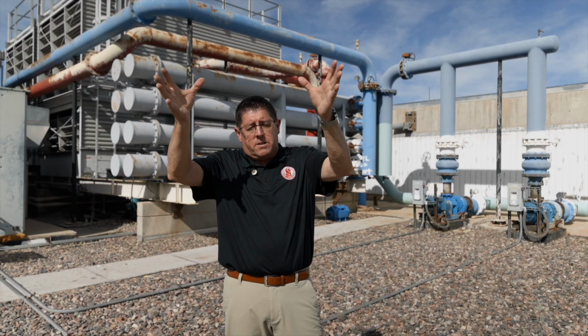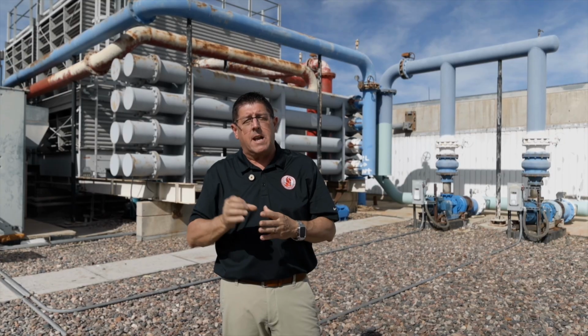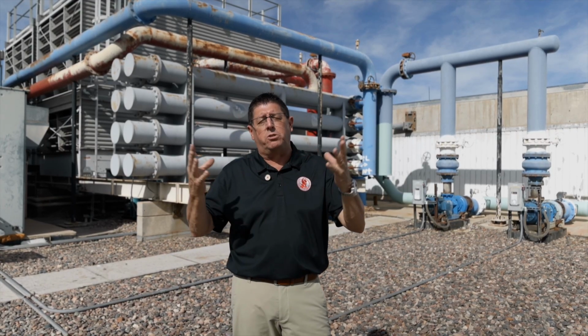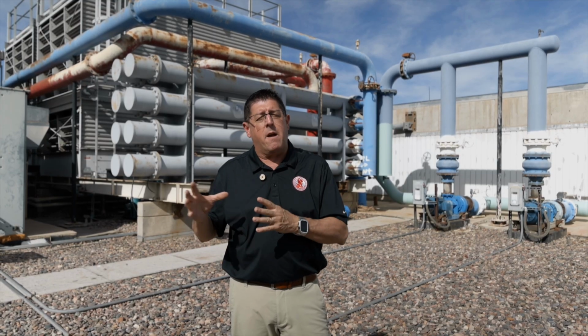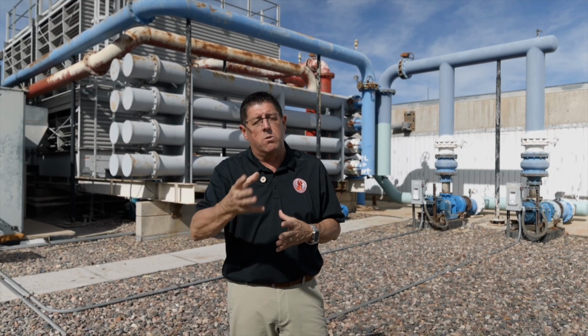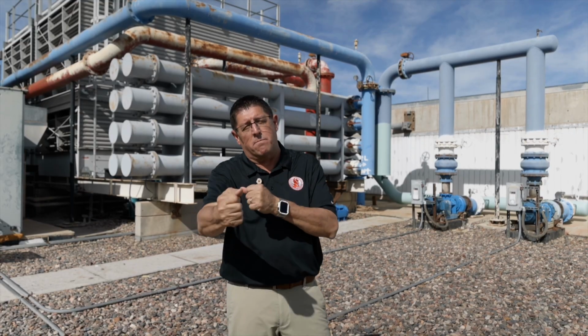If you were to look at a cutaway of a cooling tower, it's dropping the moisture or the water, and as it drops through these cells, it's taking the large drops and making them smaller drops and atomizing it. And as it atomizes, it's actually producing or offing that heat up to the atmosphere. And through evaporation, by the time that water hits the bottom of that cooling tower, it actually is cool and is being used to pump through the rest of the building to be used as that catalyst of heat movement from the interior to the exterior.